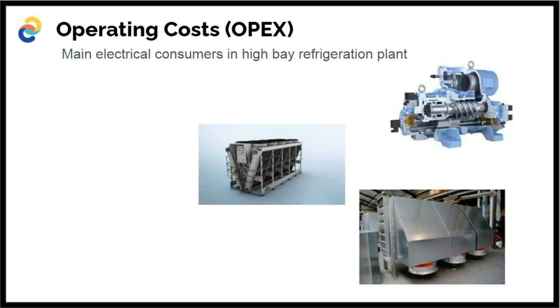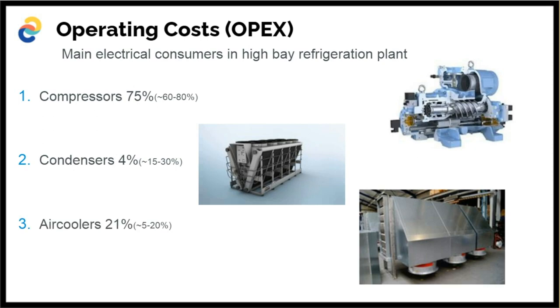Now, because we're talking about electrical costs and operating costs, what are the main consumers? Well, of course, that's typically the compressors. And in a high bay situation, we call them a high bay, these high-rise logistic centers, the compressors are by far the biggest. Condensers, not that much. But the air coolers, they also are much higher than you would expect. Big air coolers, lots of air, lots of fans.